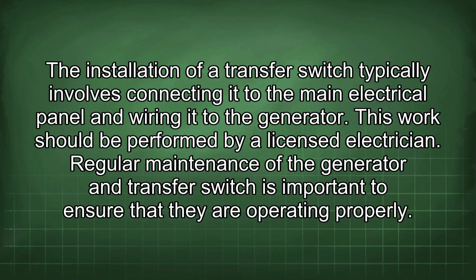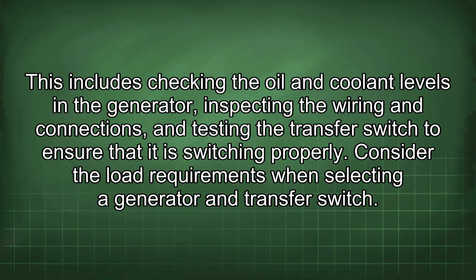The installation of a transfer switch typically involves connecting it to the main electrical panel and wiring it to the generator. This work should be performed by a licensed electrician. Regular maintenance of the generator and transfer switch is important to ensure that they are operating properly. This includes checking the oil and coolant levels in the generator, inspecting the wiring and connections, and testing the transfer switch to ensure that it is switching properly.